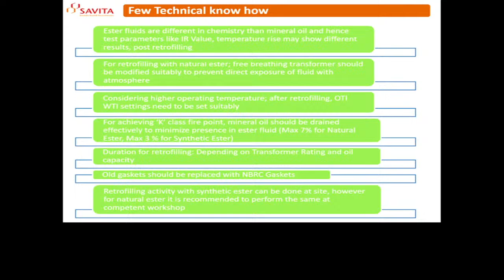You have to ensure that while removing the mineral oil from the transformer, you try to remove it and drip it as much as possible, so that there is not more than 7% of traces of mineral oil remaining. Otherwise, even though ester and mineral oil are miscible, the fire point of the composite oil sample will come down.